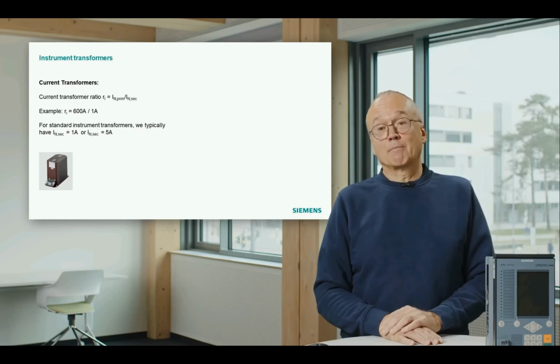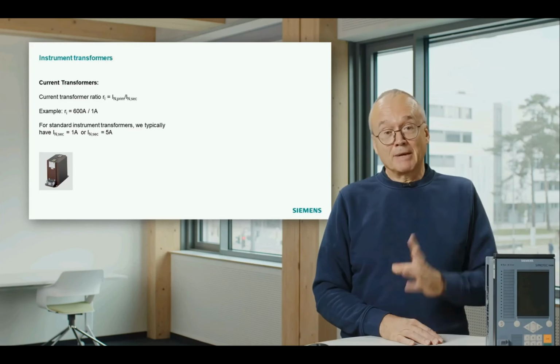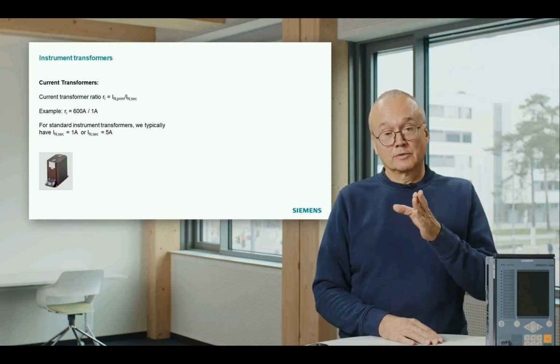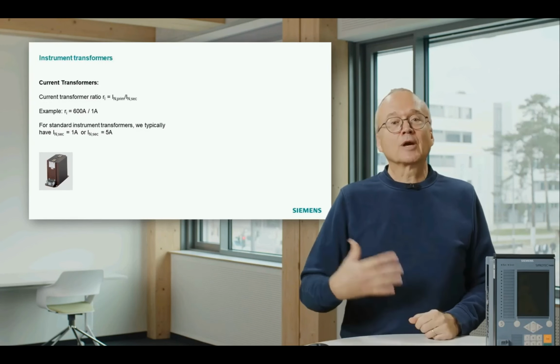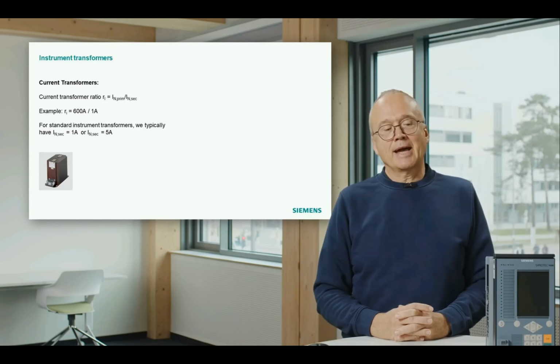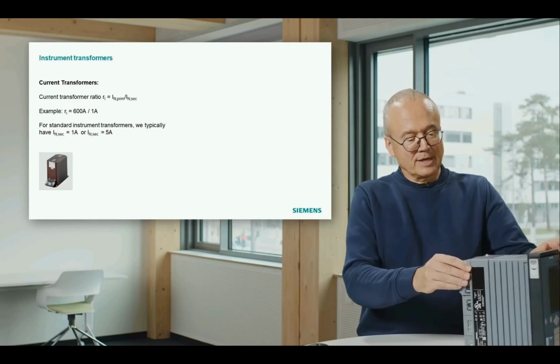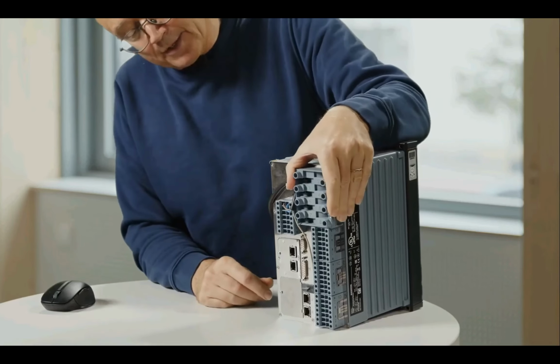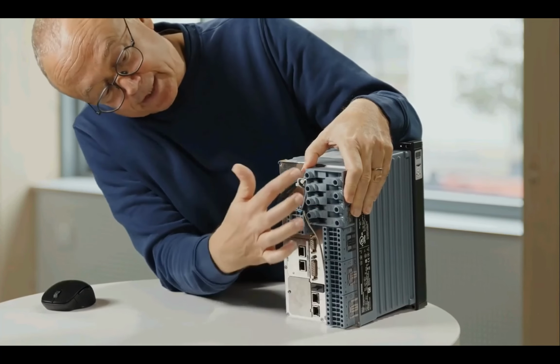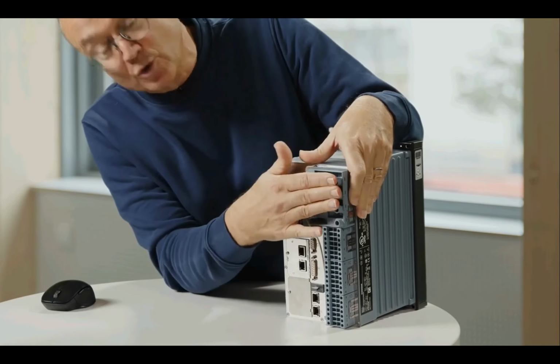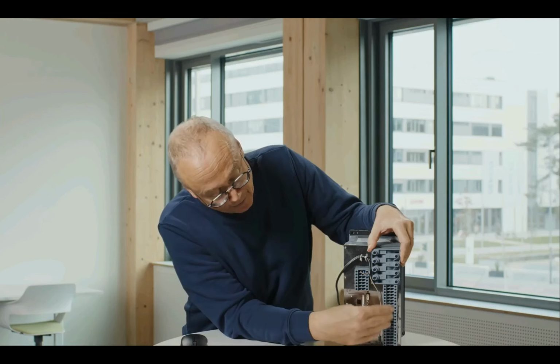And 1 amp and 5 amp are pretty high currents. Imagine these values are the current values for rated current, normal operation. And if you have a short circuit, you have, of course, much higher currents. And that is the reason if you look into our protection relays, that is a terminal block where the current is connected. Actually, you see 2 things. You see the terminal blocks where you connect the current are much bigger than the other terminal blocks. And the reason behind that is that they must be able to carry the high current. Nominal current 5 amp. Normally the devices have to be tested to withstand 100 times nominal current for 1 second. And that would mean 500 amps for 1 second.